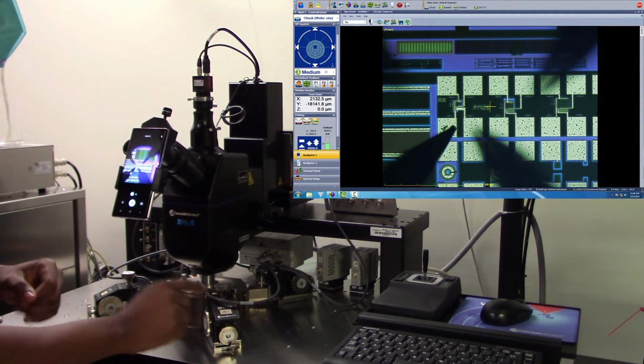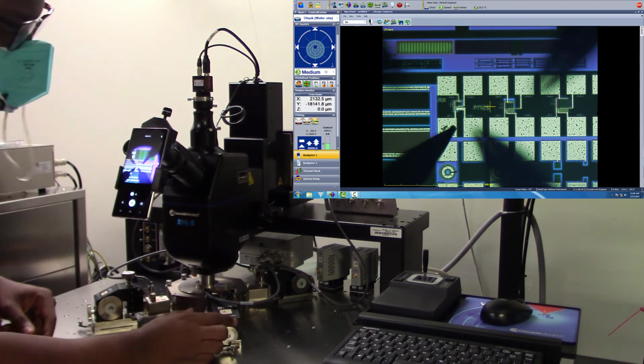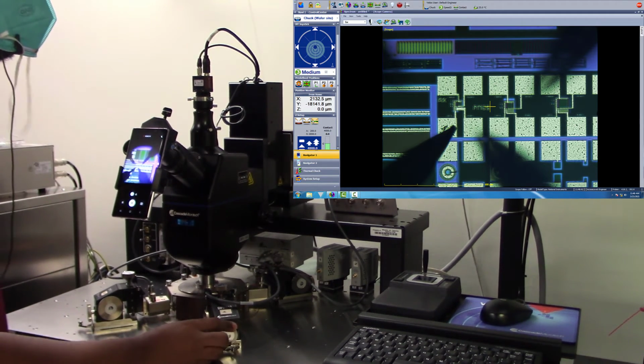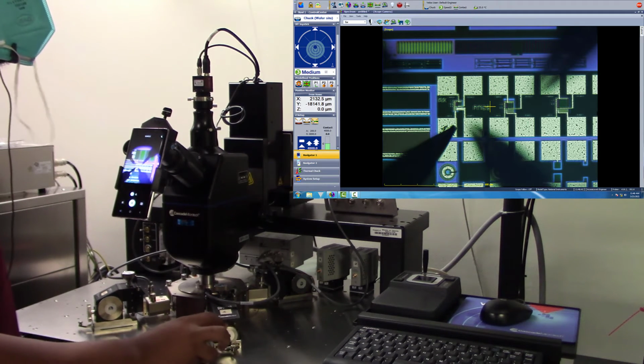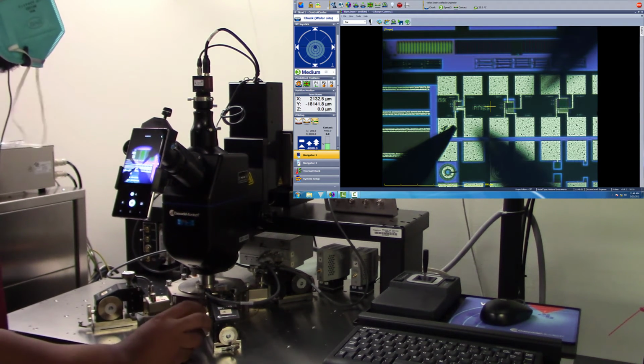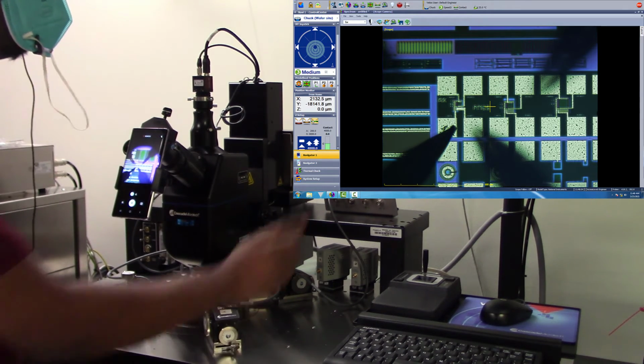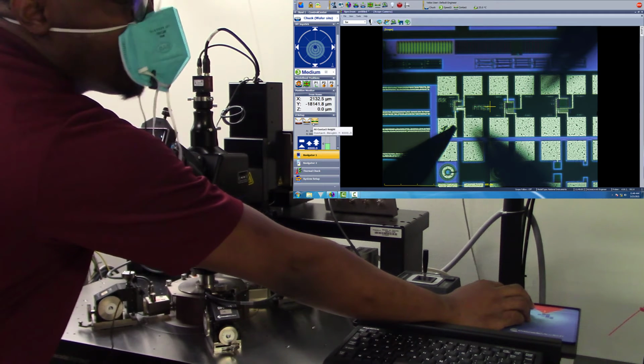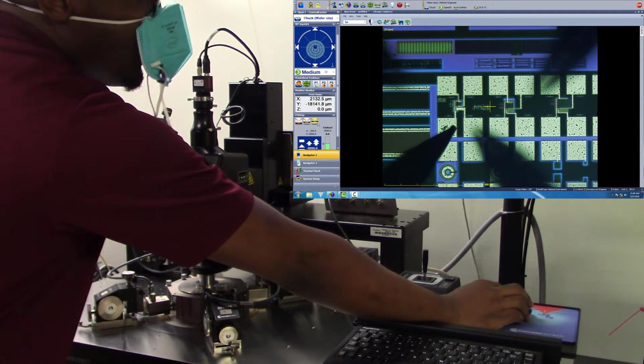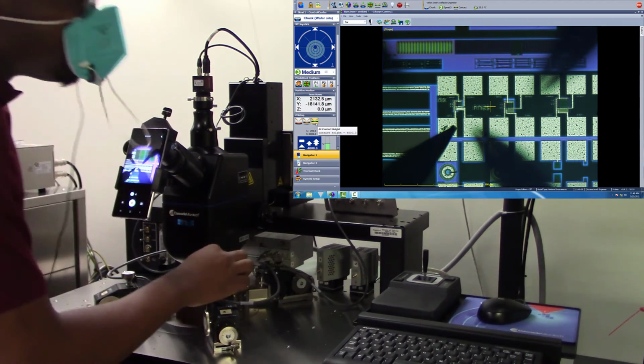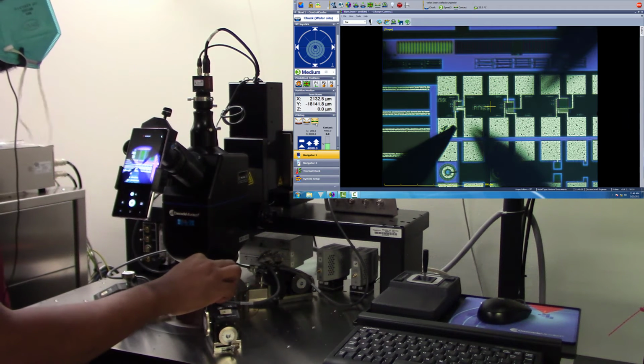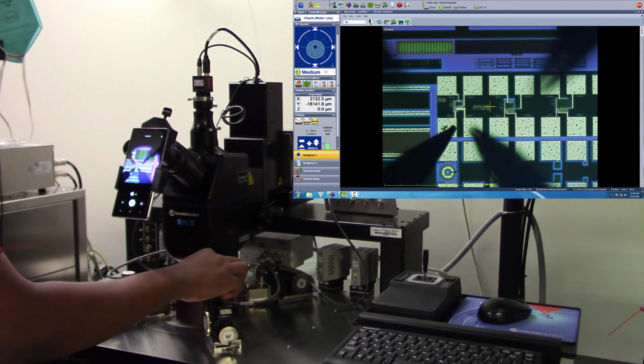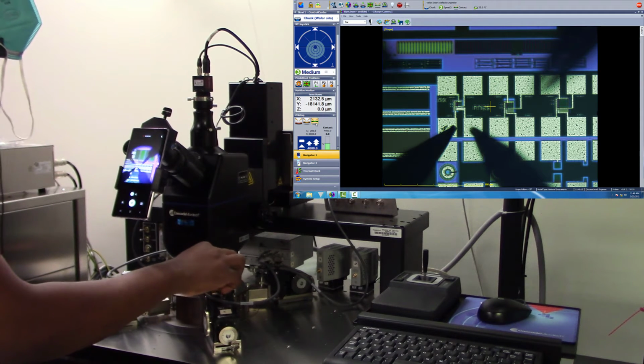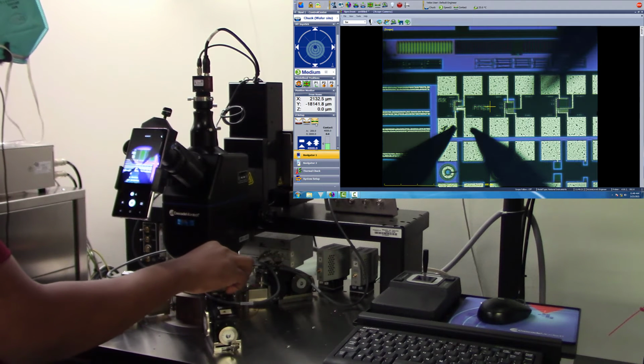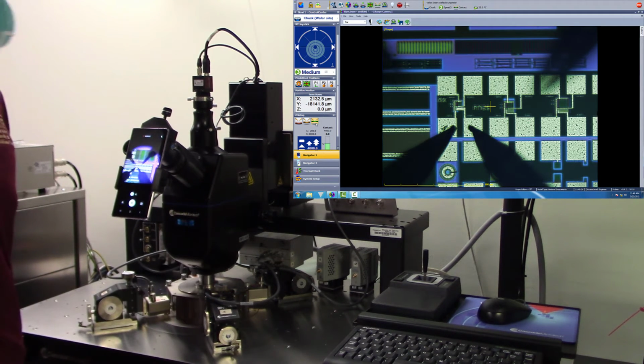I'm going to do the same thing using these micropositioners to land this probe tip on my sample. First of all, position my Y directional movement, or the Y position of my probe tip, at the edge of my device. Use my X to realign it if I need to, and verify that I'm in contact mode, at the contact height on my control center icon on my software. Then gradually land my probe by rotating your Z micropositioner clockwise until you see a gentle slide on your device. So that is the slide we are expecting.